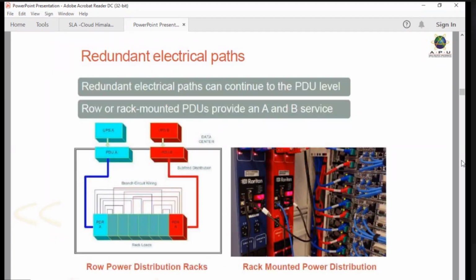Redundant electrical path can continue to the PDU level. Right from the utility all the way to your PDU, the whole path is redundant. Row or rack mounted PDUs provide an A and B service. If you see in the figure, there is one red and another blue line, and both of them are connected to each of the servers, providing an additional path.